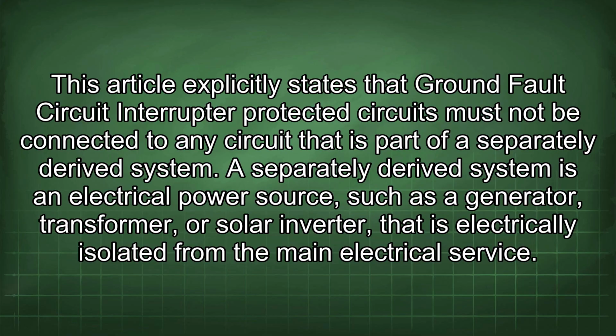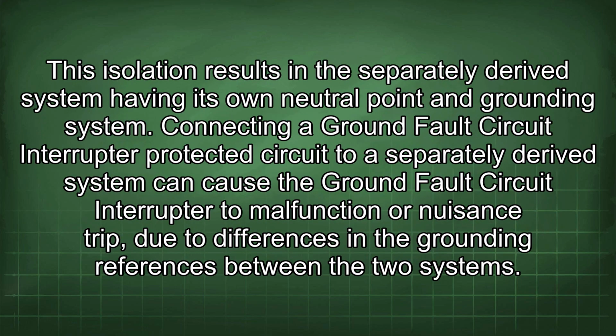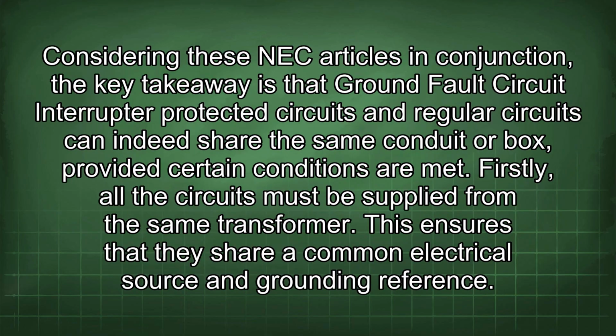A separately derived system is an electrical power source, such as a generator, transformer, or solar inverter, that is electrically isolated from the main electrical service. This isolation results in the separately derived system having its own neutral point and grounding system. Connecting a ground fault circuit interrupter protected circuit to a separately derived system can cause the ground fault circuit interrupter to malfunction or nuisance trip due to differences in the grounding references between the two systems. Considering these NEC articles in conjunction, the key takeaway is that ground fault circuit interrupter protected circuits and regular circuits can indeed share the same conduit or box, provided certain conditions are met.